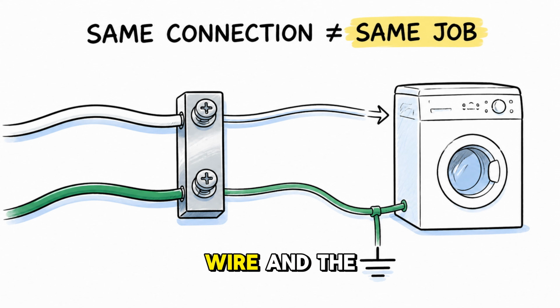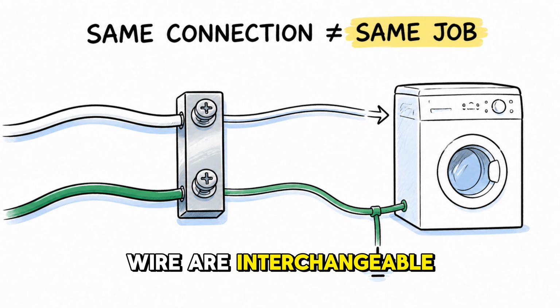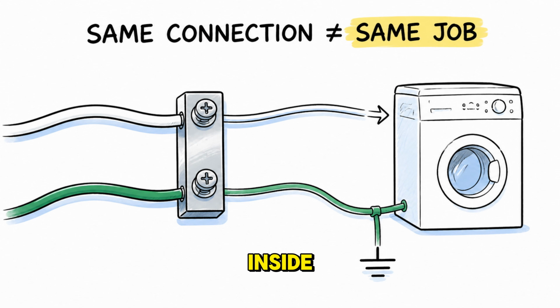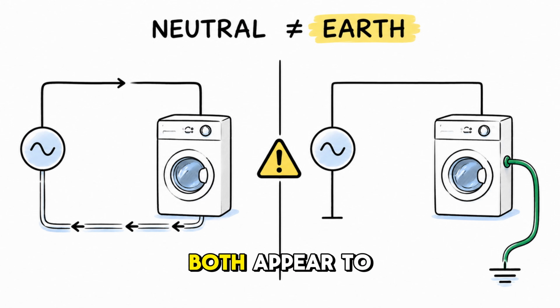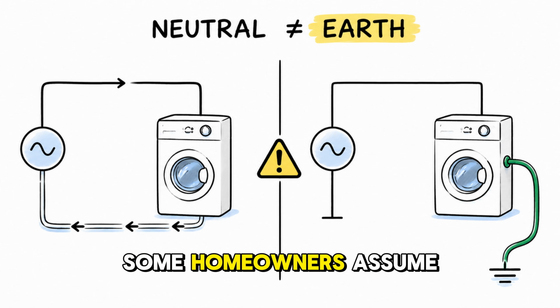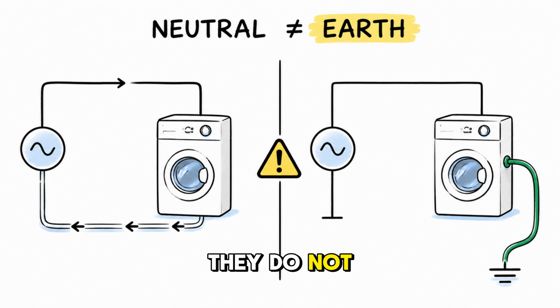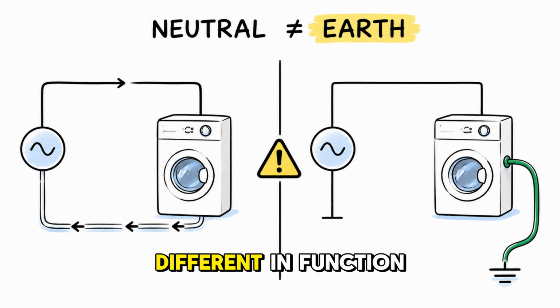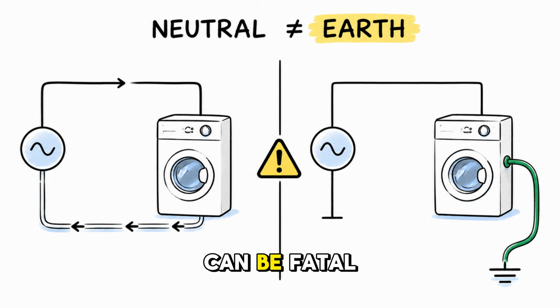People assume the neutral wire and the earth wire are interchangeable because they connect to the same bus bar inside your main service panel. Both appear to go to the exact same place. Because of this, some homeowners assume they do the same job. They do not. They are fundamentally different in function, and confusing them can be fatal.